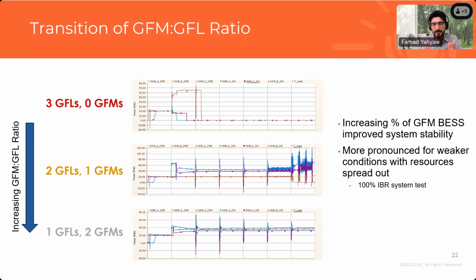For these disturbances, we weakened the system and applied a strong three-phase-to-ground fault. With one GFM, shown in the middle plot, the system was stable up to a certain threshold and then became unstable. When we additionally increased the GFM, we saw a stable response throughout the whole simulation.